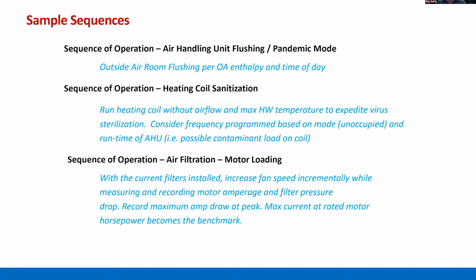Heating coil sanitation. There are several studies out there, similar to Legionnaires' disease, that once you hit about 150 degrees, it does kill all biological life forms. We are running a heating coil sanitation cycle at 1 a.m. where the fan is off and we're just heating up the air handling casing. Most filters can take up to 180 degrees of heat, so we don't see any degradation. The only worry may be some wiring, but that shouldn't be a problem. So the goal is to try to kill everything in that casing, one more level of sanitation.